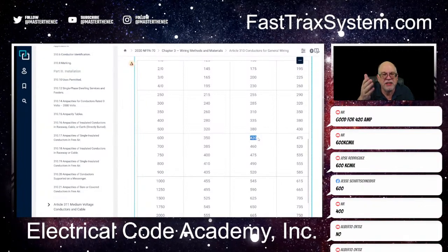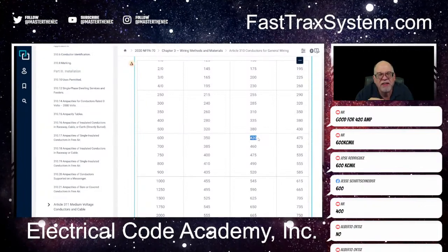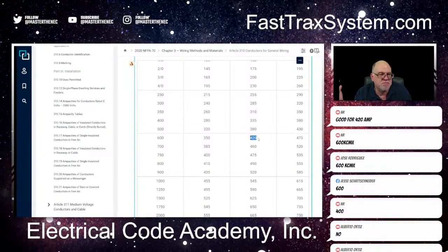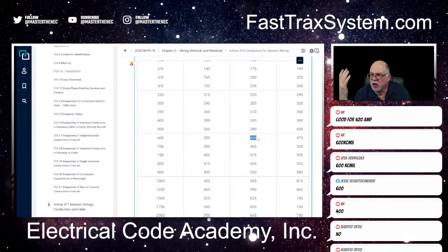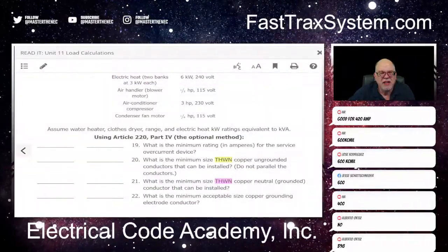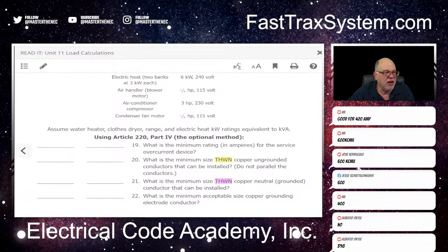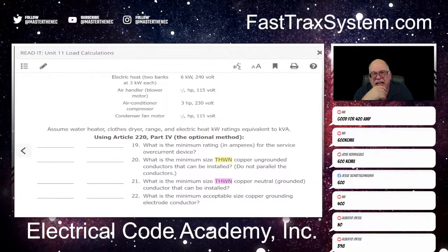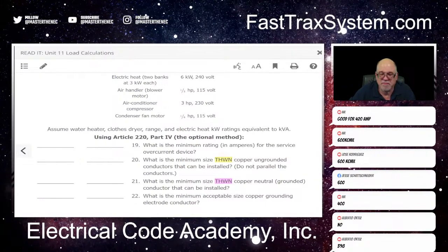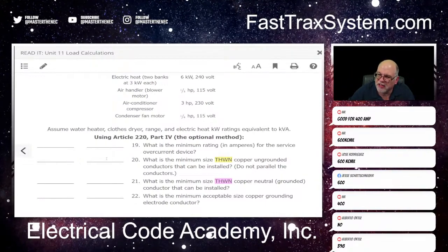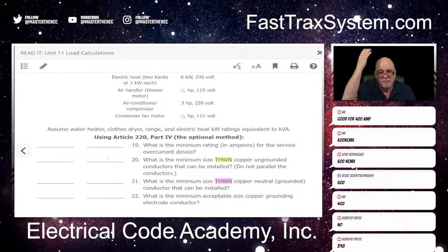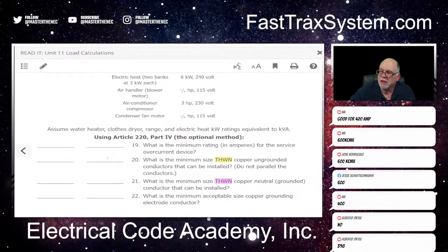Bingo. Very good. NR. Is that NR? It's NR. All right. So it's good for 420. So perfectly acceptable to handle the load that we have. Right. So back to the lesson. So again, in our case, we just need to handle 398. It handles 420 and it's perfectly okay. So this conductor right here would be a 600 kcmil. Make sense? Boom. All right.